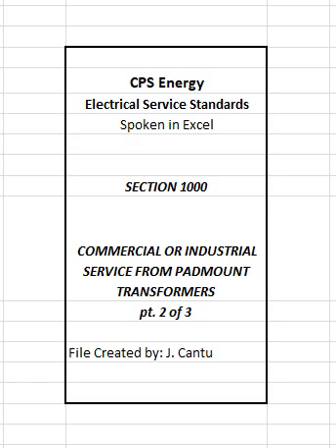4. Wireways shall not contain removable covers and shall be equipped with gasketed flanges secured by nuts and bolts suitable for the condition. Self-tapping screws are not permitted. 5. Wireways shall be constructed of corrosion-resistant steel, primed and painted. 6. CPS Energy will furnish, install, and maintain copper secondary cables from the transformer secondary terminals to the tap box. CPS Energy will furnish necessary lugs and make terminations in transformer secondary. Customer will furnish necessary lugs to make terminations in customer-owned tap box.